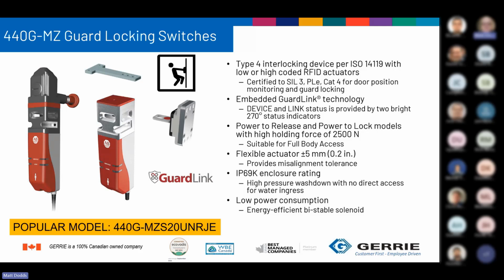I've been, again, product manager for almost 30 years. The 440G-MZ is my favorite guard locking door switch. Why is that? It's a Type 4 device, as per ISO 14119, with low or high coded RFID actuators. Just a side note, where would I use a high coded RFID actuator? In a place where there is a high probability of defeat. So if you determine that someone's going to bypass this door with a spare actuator, then you can put on a unique actuator, high coded, that needs to be taught.